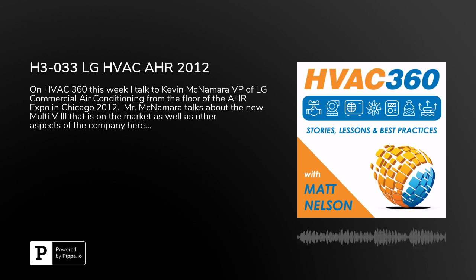One of the misconceptions a lot of folks have had is when they think of the VRF system, they don't think of the system, they think of a comparative like a chiller or a rooftop unit. They don't think about the fact that you have ductwork, large ductwork, large pumps, cooling tower, all the downstream apparatus to support the chiller. When you install a VRF system, you are truly installing a system in your building. Once that breakthrough is made, there's a lot more understanding of why it costs what it does to install, and why it costs what it does from a long-term cost of ownership perspective, as far as being lower cost. But I have yet to meet with anyone who says they made a mistake by putting this in their building.